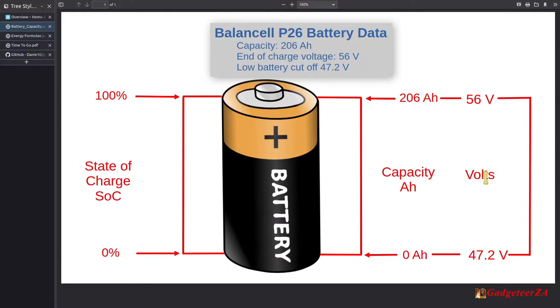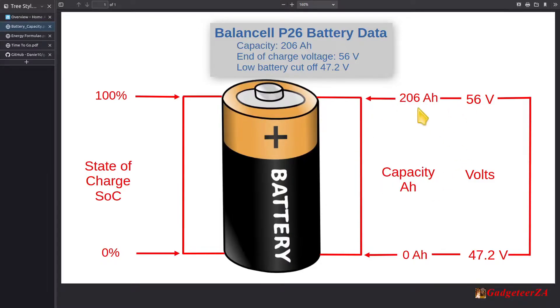To relate it to voltage again: the cutoff voltage specced for this battery is 47.2, so assume that's the empty point — when it reaches that the system shuts down. And 56 volts we can assume is the full voltage. I'm not using voltages for these calculations, but if your system only has volts and current, you could still apply what I'm talking about here and adapt your formulas accordingly for volts and amps.